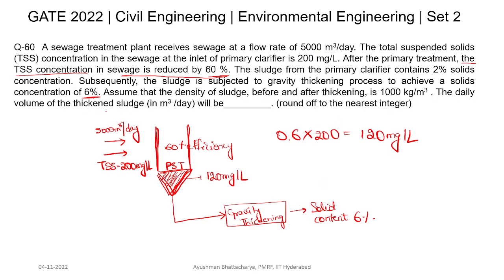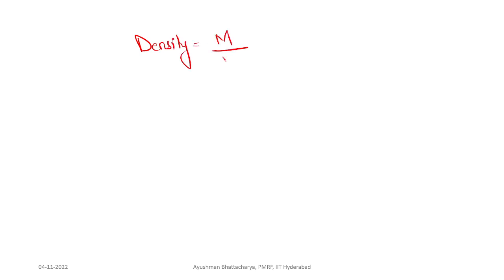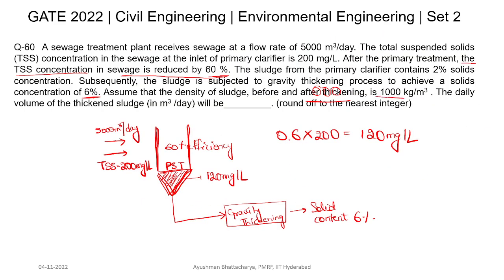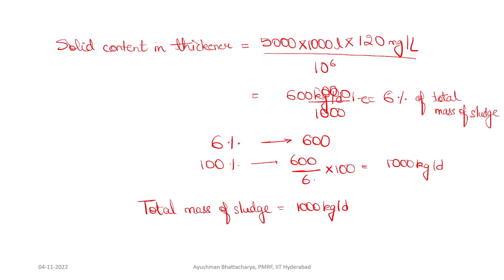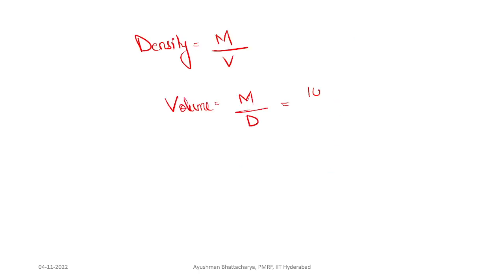The question asks for the daily volume of the thickened sludge. We know that density = mass ÷ volume, so volume = mass ÷ density. The total mass was calculated as 10,000 kg per day. The density is given as 1000 kg per m³. Therefore, volume = 10,000 ÷ 1000 = 10 m³ per day. I hope this is clear. Thank you.